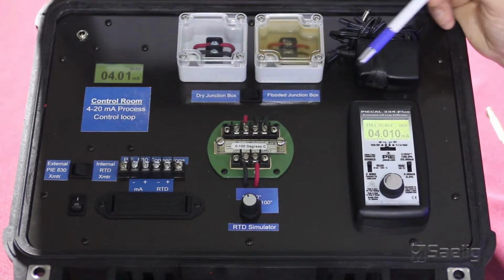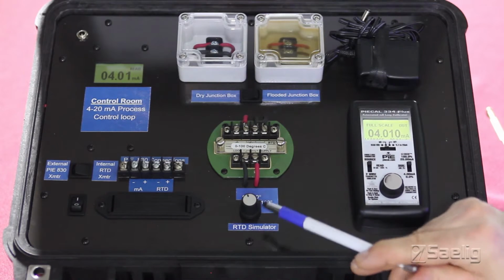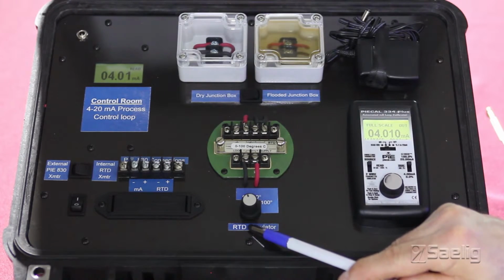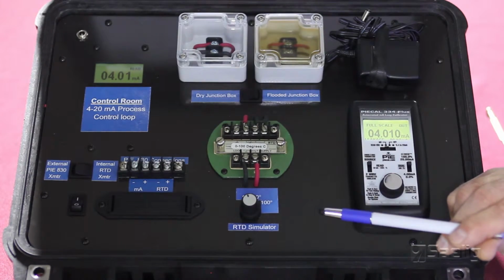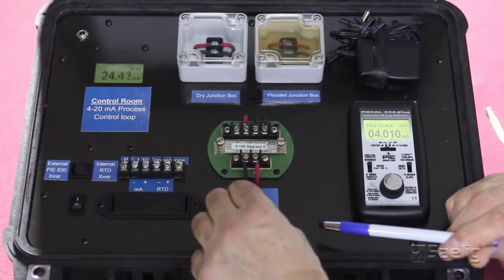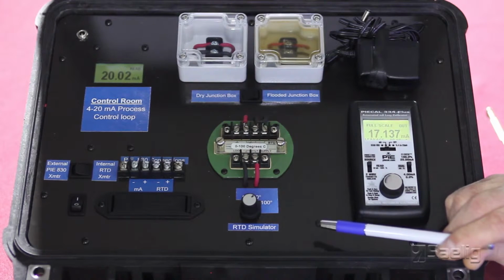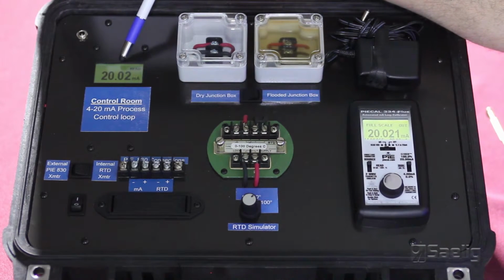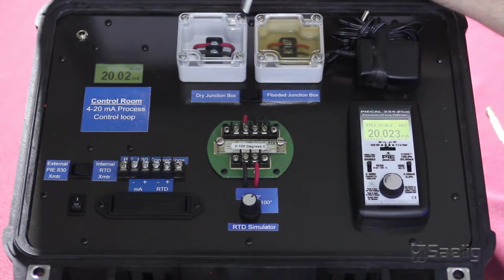Our control loop is set up with 0 degrees being our low signal, corresponding to 4 milliamps on our control room, and a high signal of 100 degrees being 20 milliamp output. This loop is now in control.